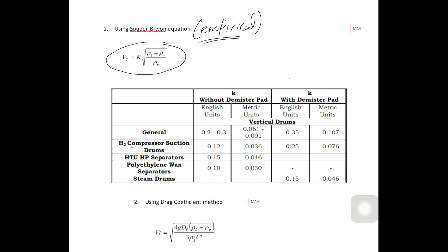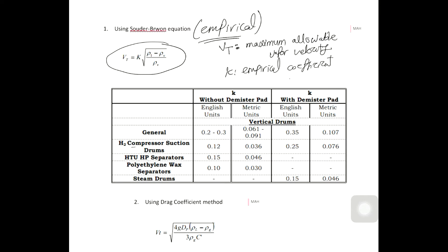The Vt is the maximum allowable vapor velocity. The K is the empirical coefficient and has the same dimensions as velocity. The following table contains the values of K. If this separator is being used in general surface service, the value of K is 0.2 to 0.3 in English units.